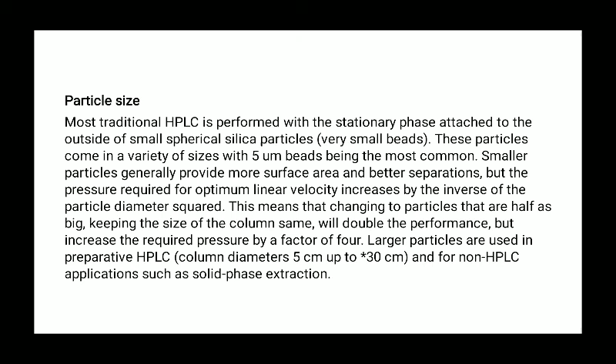This means that changing to a particle that is half as big, keeping the size of the column the same, will double the performance but increase the required pressure by a factor of 4. Larger particles are used in preparative HPLC and for non HPLC applications such as solid phase extraction.